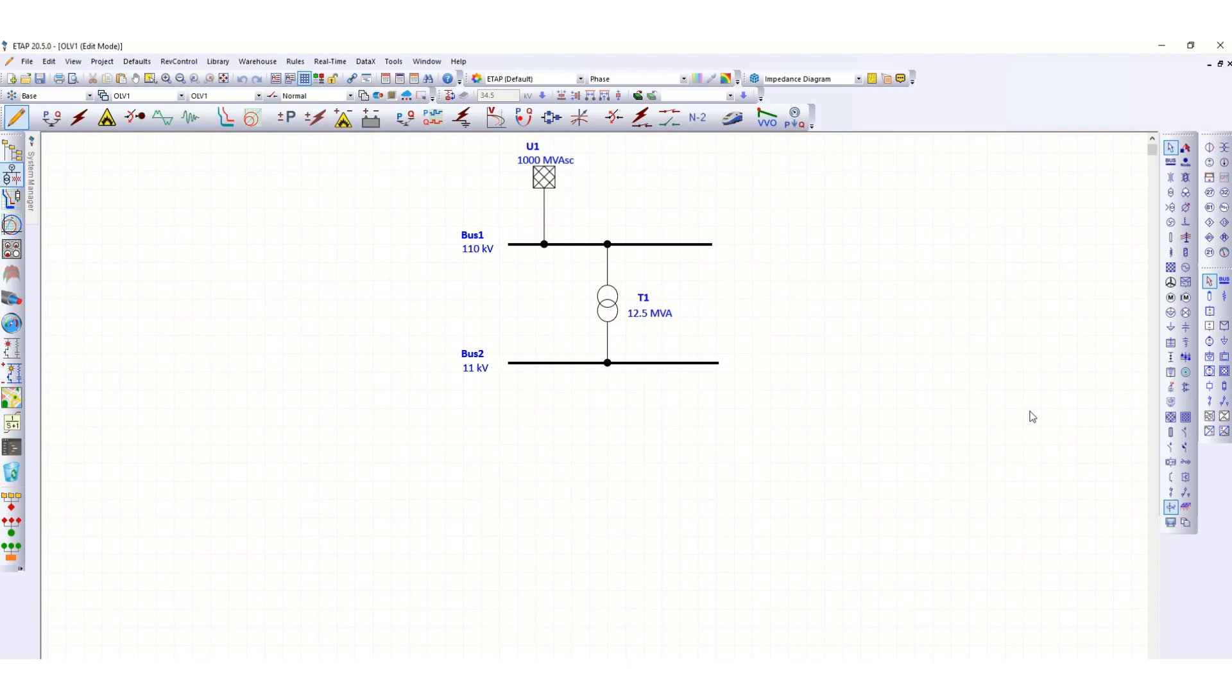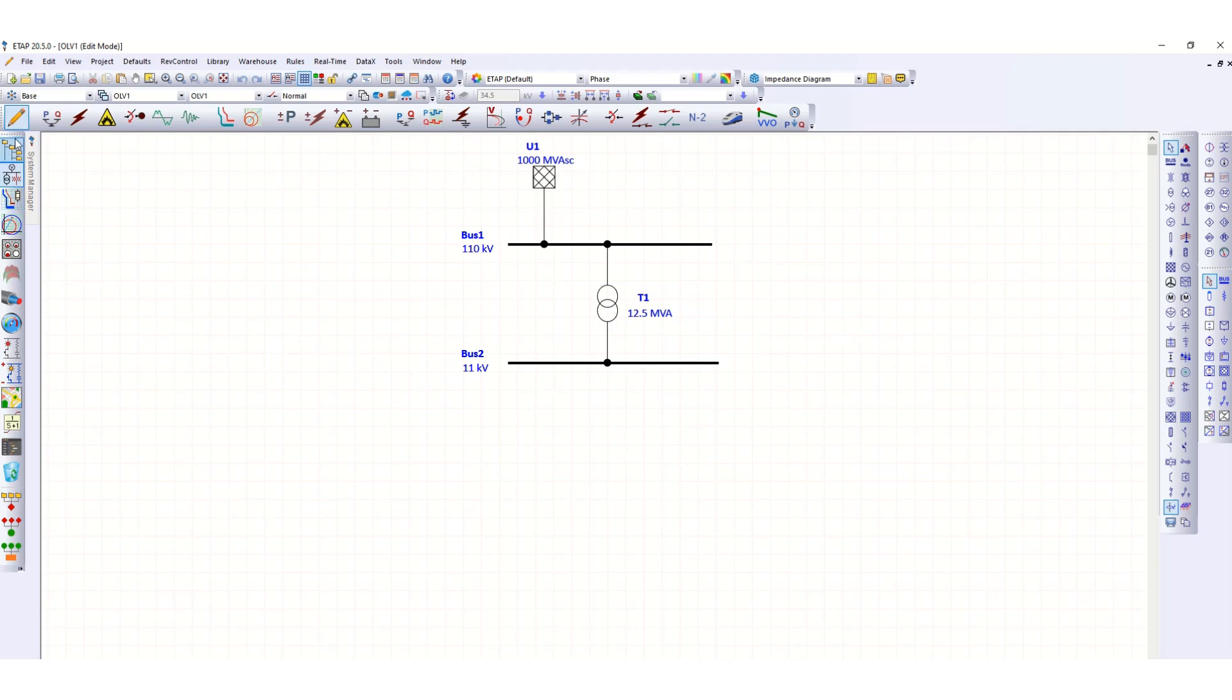In this Arc Flash analysis tutorial, we have drawn a simple single-line diagram. A 110 kV grid is connected to a 110 kV bus, with a step-down transformer. Let's draw a balanced part to run this Arc Flash analysis.